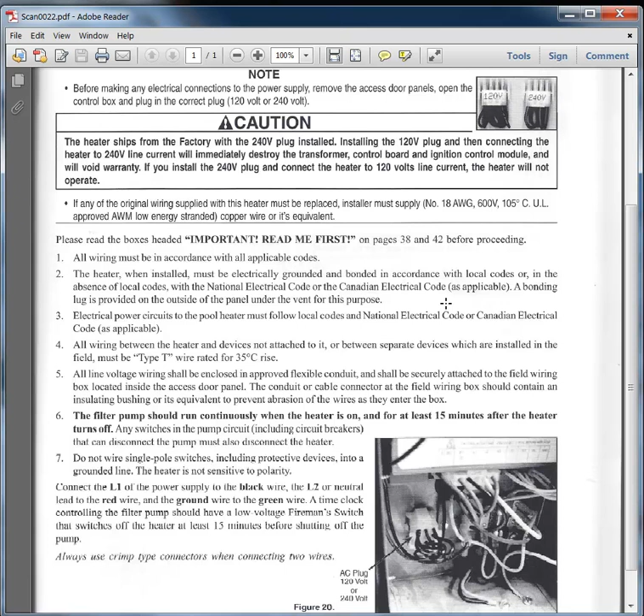Alright, this is my biggie, should be highlighted - this is number one. The heater, when installed electrically, grounded and bonded. If you don't know what that is, or your licensed electrician doesn't know what bonding is: it goes to your pool equipment, the pool pump, whatever. It's a bare copper wire, not a stranded wire, to the bonding lug. Grounding and bonding are two separate things.